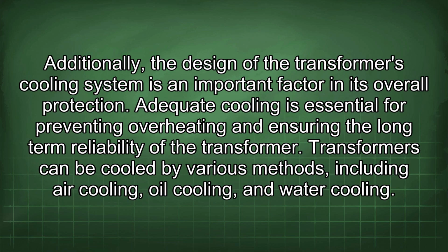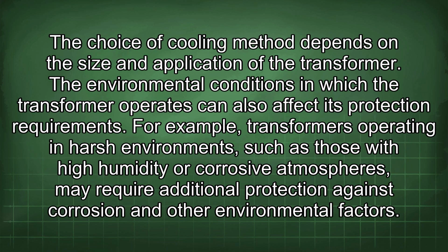Additionally, the design of the transformer's cooling system is an important factor in its overall protection. Adequate cooling is essential for preventing overheating and ensuring the long-term reliability of the transformer. Transformers can be cooled by various methods, including air cooling, oil cooling, and water cooling. The choice of cooling method depends on the size and application of the transformer.